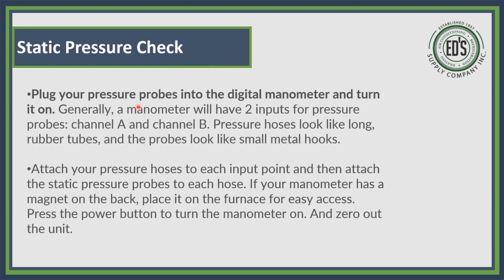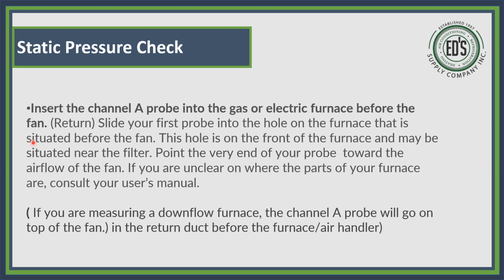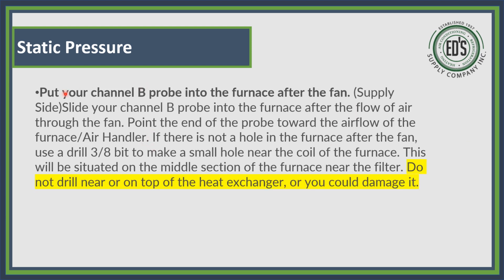All right, so when you do this, we're going to recap real quick what I just said. You've got two inputs for pressure. Channel A is return, channel B is supply, channel A is P1, channel B is P2. Make sure you use the rubber tubes and the metal hooks, and make sure you have zeroed out your manometer. You put A1 or P1 in return. All right, put B2 or P2 in the air handler supply. You can use a 1/4-inch drill, but I think it's a little bit bigger. You can go 3/8. You don't want to go a 1/2 inch, but go 3/8. Fits in and out real good.